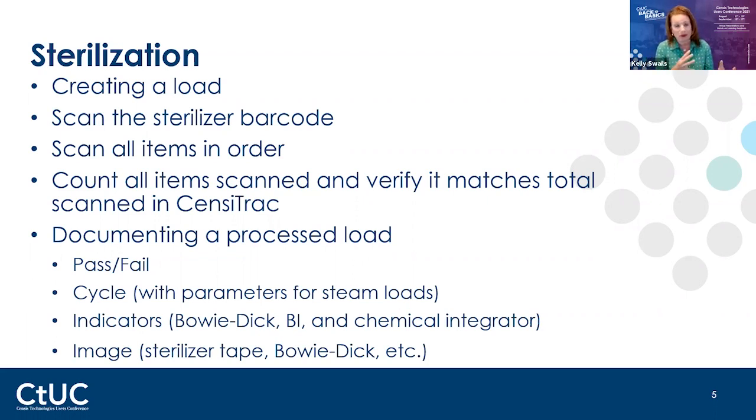If I have to physically walk over and scan sterilizer 1, because that's what I want to put it in, I get over there and I'm like, oh, there's a load going. I didn't realize that. Or there's a load cooling and I can't take it out yet. So now I'm going to use sterilizer 2. So I go scan sterilizer 2. I've got my correct one because I had to physically walk over and scan it. So I encourage everyone, get rid of those sheets of paper and walk over and scan them.